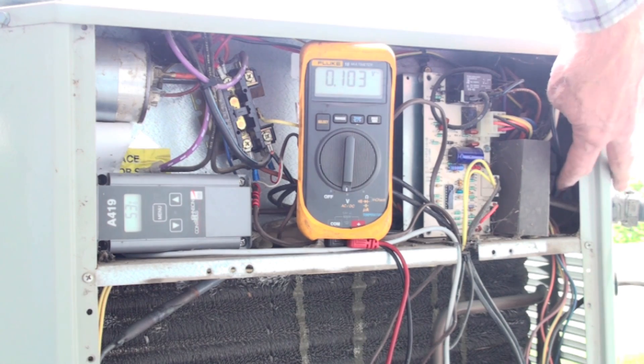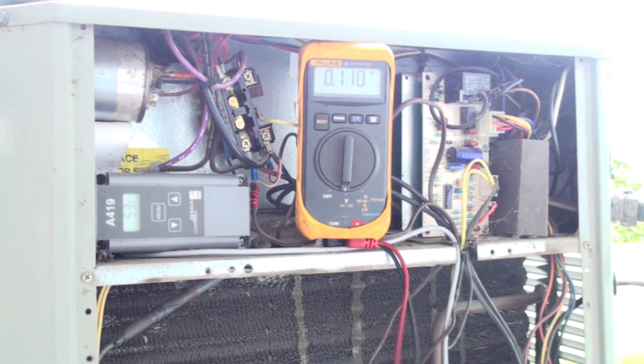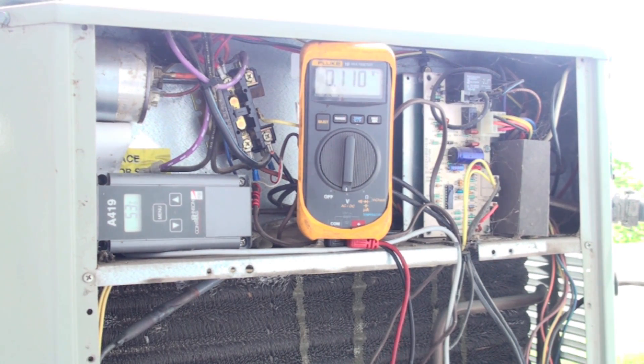Remember — if you're working in here, you either pull your disconnect at your fuse at your fusible disconnect or get the breaker inside. Don't start sticking your fingers around in here trying to find out where wires go until you kill the power.